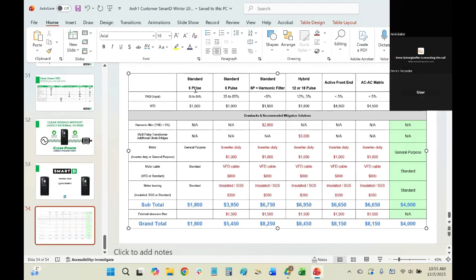If you're just up against a standard 6-pulse drive that's naked, with no filtration on it whatsoever, we're going to be about double the cost of that, because we're including line and load filtering at a high level. But the moment you start adding any kind of reactor, or the costs for special cabling, different installations and things like that, we start to become on par, bring that cost even. Then as you add more and more filtering, we're now the cheaper option, and so on and so forth.